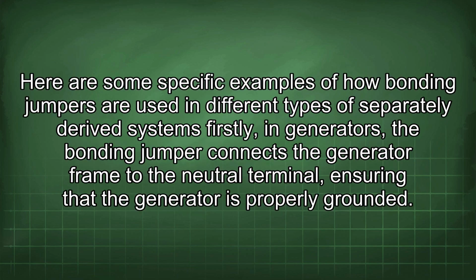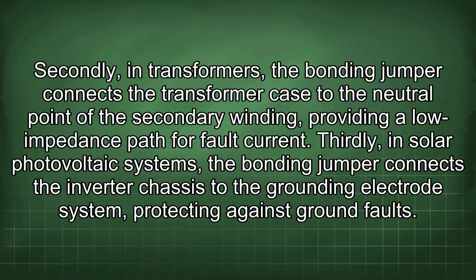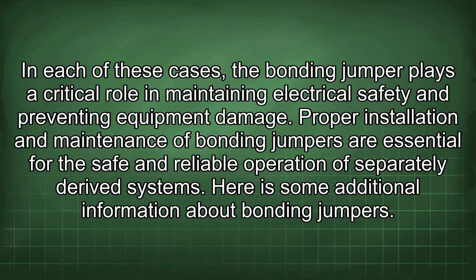Here are some specific examples of how bonding jumpers are used in different types of separately derived systems. Firstly, in generators, the bonding jumper connects the generator frame to the neutral terminal, ensuring that the generator is properly grounded. Secondly, in transformers, the bonding jumper connects the transformer case to the neutral point of the secondary winding, providing a low impedance path for fault current. Thirdly, in solar photovoltaic systems, the bonding jumper connects the inverter chassis to the grounding electrode system, protecting against ground faults. In each of these cases, the bonding jumper plays a critical role in maintaining electrical safety and preventing equipment damage. Proper installation and maintenance of bonding jumpers are essential for the safe and reliable operation of separately derived systems.